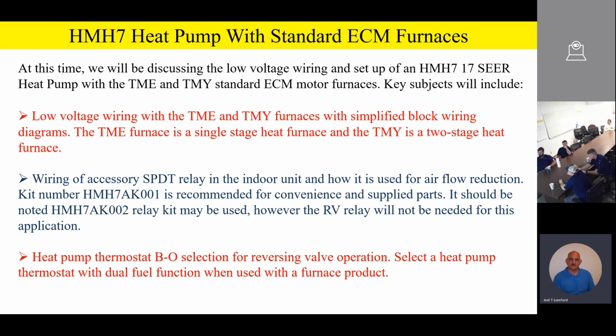So at this time, let's go ahead and jump into some furnaces then. We're going to be looking at the TME and the TMY standard ECM furnace. And just like we did before, we're going to have some simplified block wiring diagrams to look at, and we're going to take it wire for wire. And we're going to be featuring that single pole double throw relay again in the indoor unit, that what we call the HMH. The 001 kit is recommended for all the convenience and supplied parts.